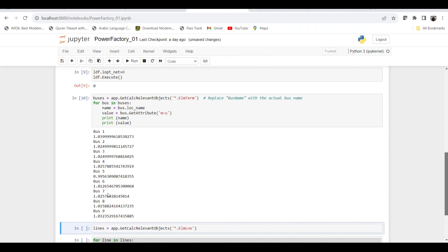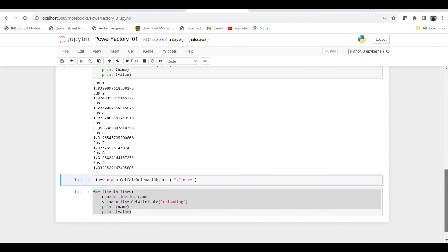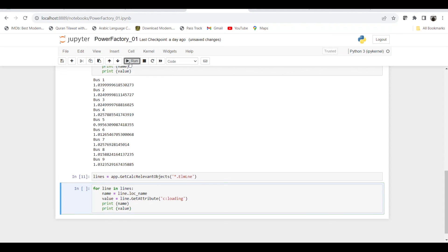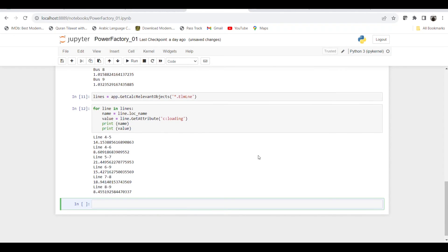In the same way, if we want to get the values of all line elements — transmission lines or cables — within our system, instead of 'ElmTerm' we use 'ElmLne'. In upcoming sessions we will show you how to check what element type a particular piece of equipment falls into using the GUI. Once we run this, all line element objects are called. We iterate through each line element, printing its name and the loading percentage. You can see the percentage loading of all lines in the case.